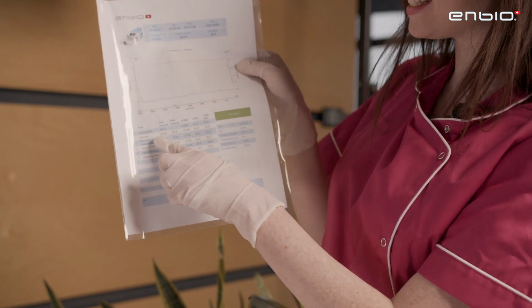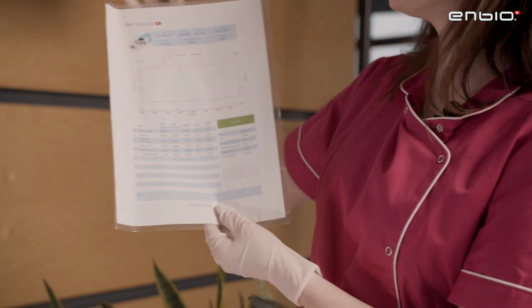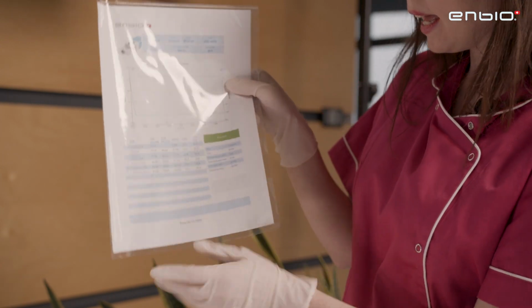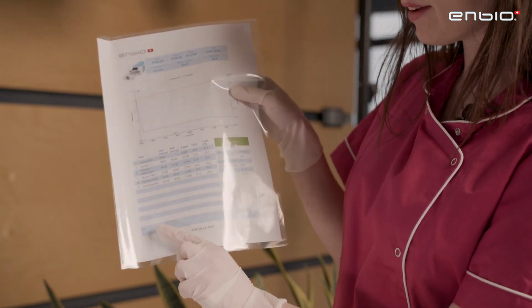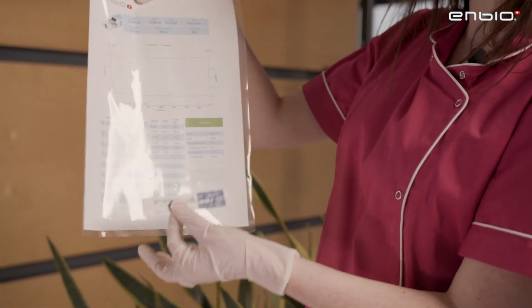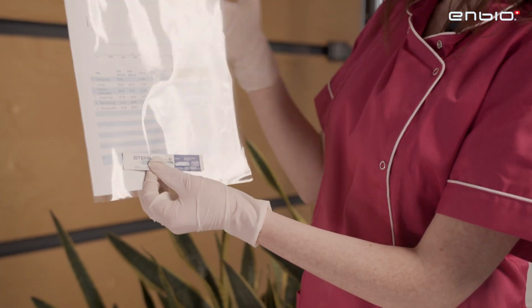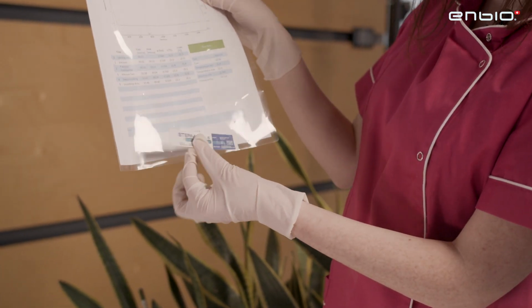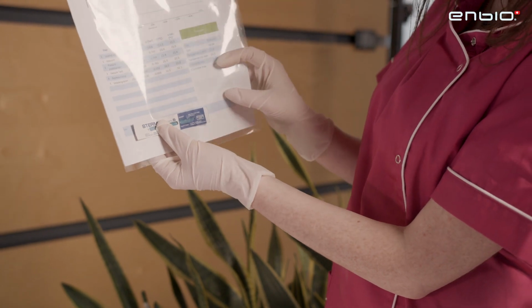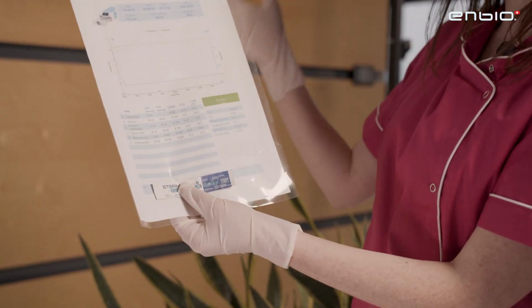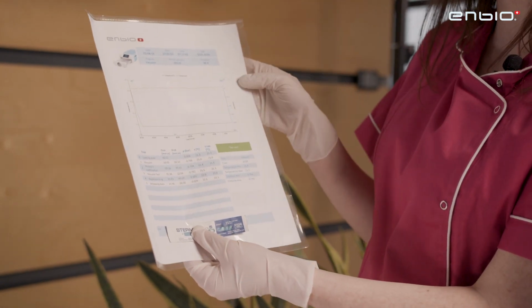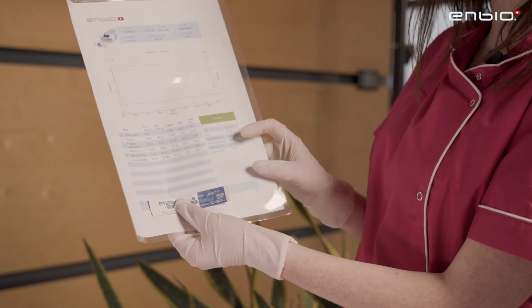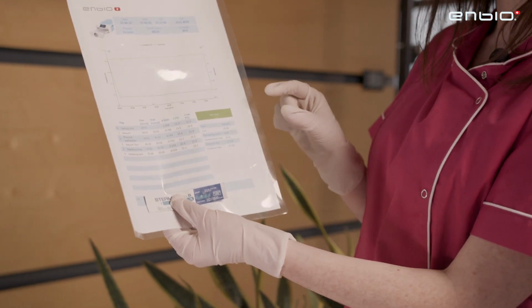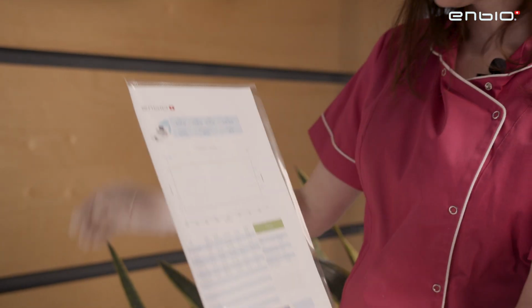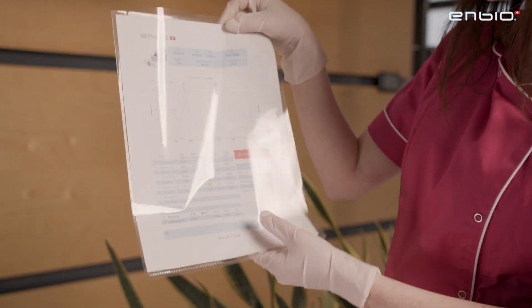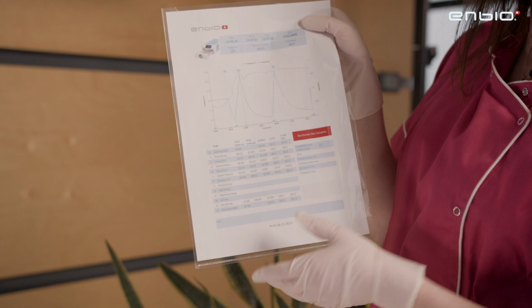And here we can see the stages that the autoclave performed during the sterilization. And after each sterilization process, you have to put here the chemical indicator that you used in order to prove that the sterilization process was done properly. So this has to be put here. And here we have some empty space where you can add some additional information regarding the sterilization process that you did. For instance, here you can see how many sterilization pouches you used and how many tools were in each sterilization pouch.